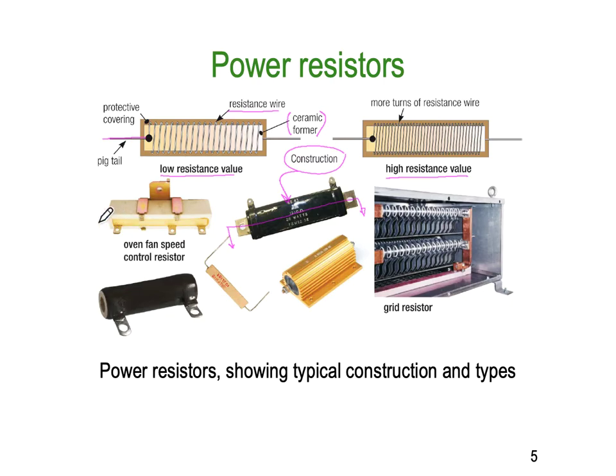Resistors also come in a ceramic box with tabs at either end giving the full resistance value, and a tapped-off terminal in the middle giving a second resistance value. By connecting across different terminals you get different resistance values. This construction is used as a fan speed controller — putting resistance in the path of the fan causes a voltage drop which reduces the fan speed.